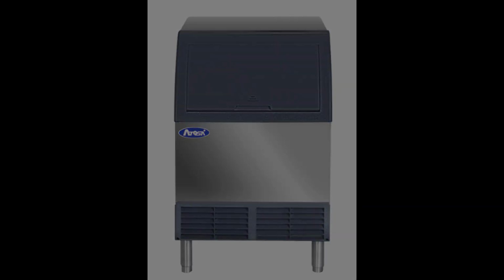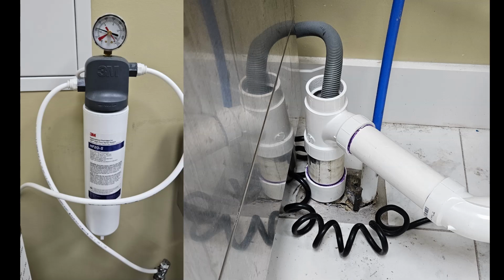Let's dive in. To begin with, you will need to make sure that a certified plumber has installed a water filter and the location where the unit will be set up has a 120-volt power outlet and an open-air floor drain. The ice machine drain will need to be uphill from the floor drain so that the water the ice machine drains out will flow downhill to the drain. Do not install the drain line uphill, this will cause standing water in the bottom of the ice bin.